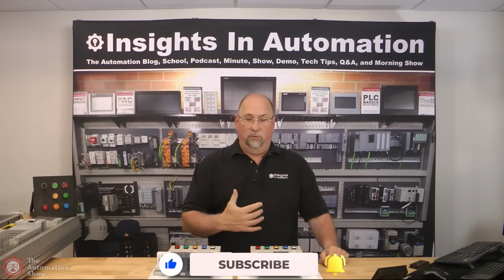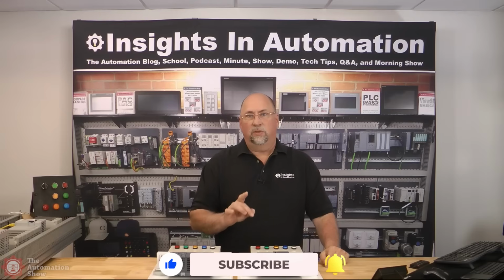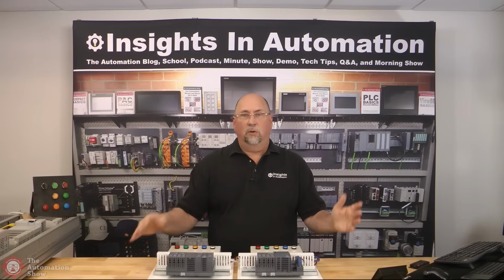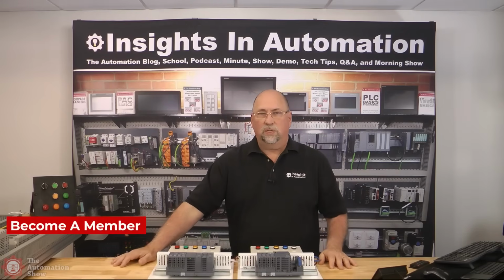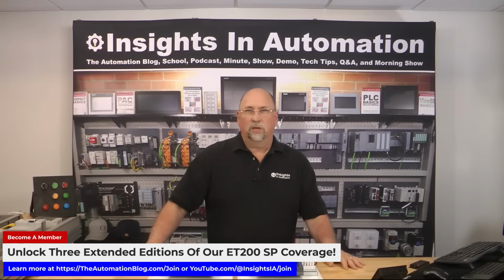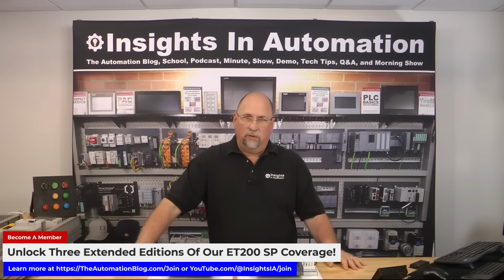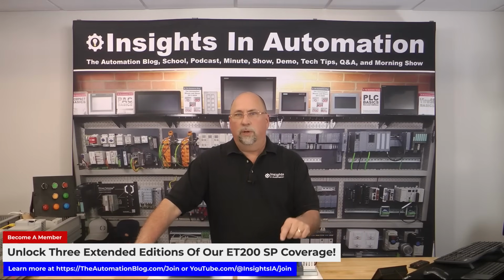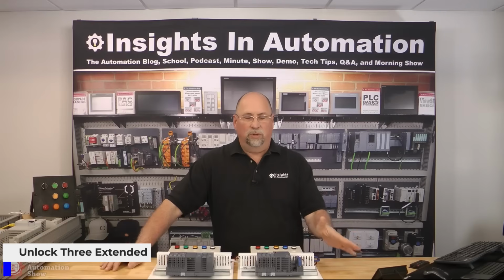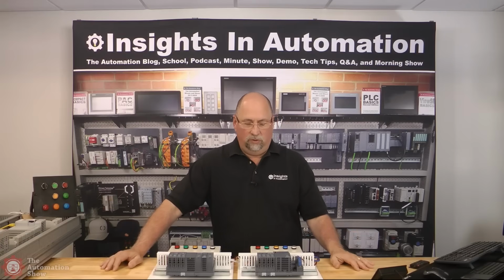So that is how easy it is to commission a brand new S7-1500 ET 200SP CPU, right? But the advantage of this is that it has all those high-end features, all those extra data types and whatnot that you would have with an S7-1500 versus a 1200. But you also have to have a memory card. And again, I had to format that to get that to work. With the 1200, you don't have to. It's optional, but you don't have to have the memory card. With the 1500, you do.